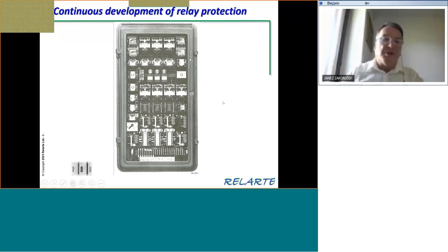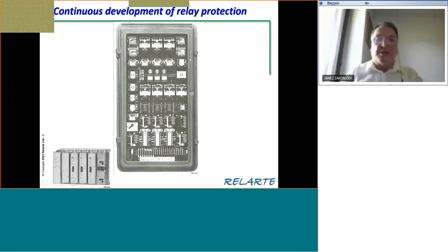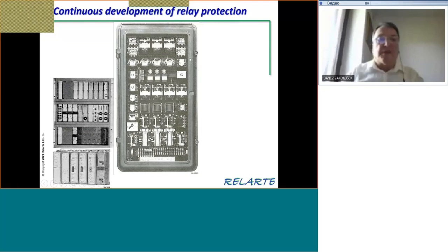Later on they started with static relays. I'll tell you about this - not because I worked there, but I have been working with ABB and also with former ASEA, which was later united with Brown Boveri to form ABB. During that period this was absolutely the leading producer of relay protection, with the highest technology. You can see here a three-phase overcurrent protection from that time, which was static protection - electronic protection, one of the fastest in the world. I will show you later on how it worked.